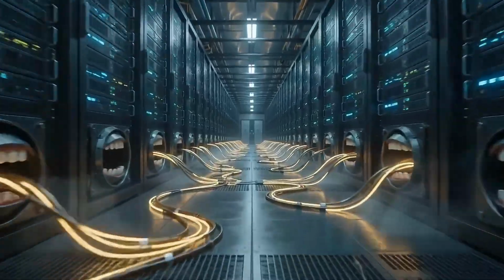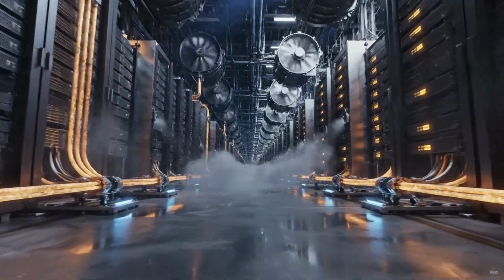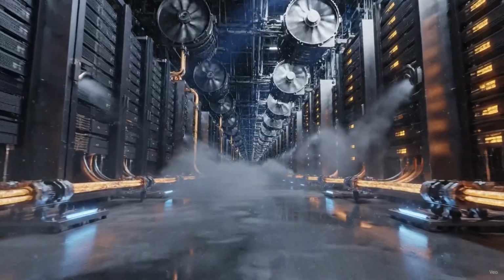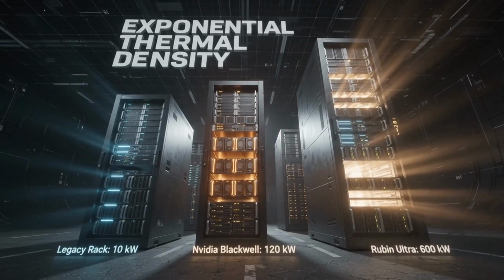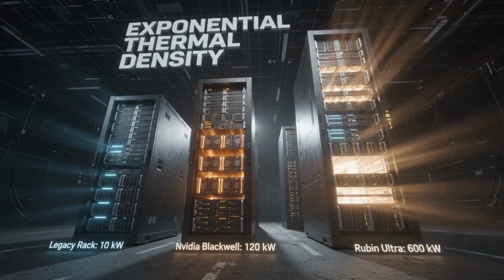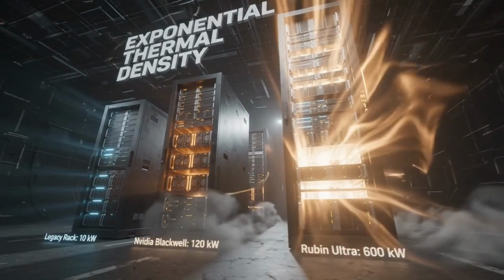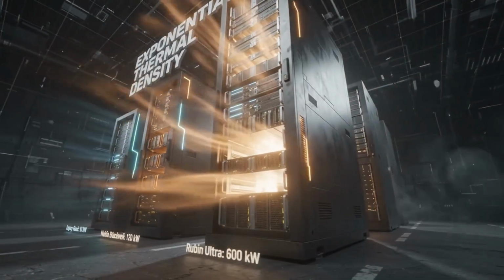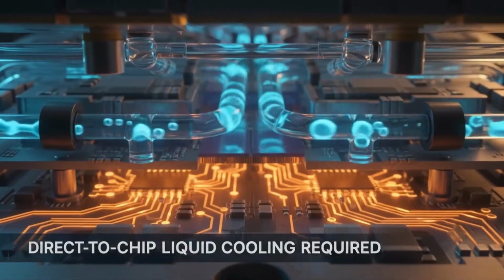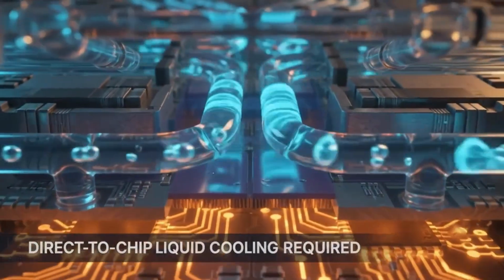A legacy data center rack, the kind that runs most of the internet today, draws about 5 to 10 kilowatts of power. The new NVIDIA Blackwell racks draw 120 kilowatts. The upcoming Rubin Ultra racks will pull 600 kilowatts. At that density, standard air conditioning physically stops working.